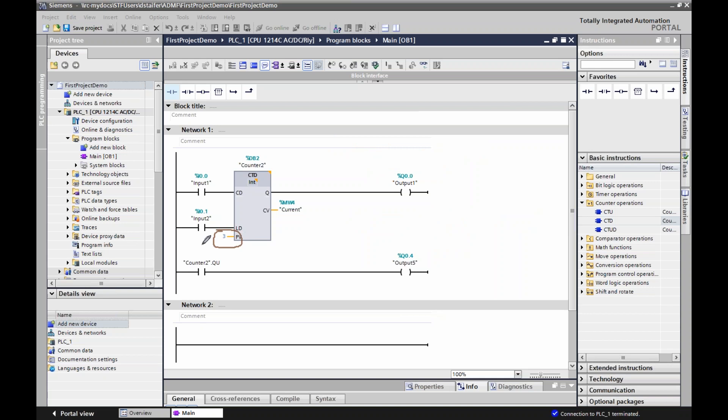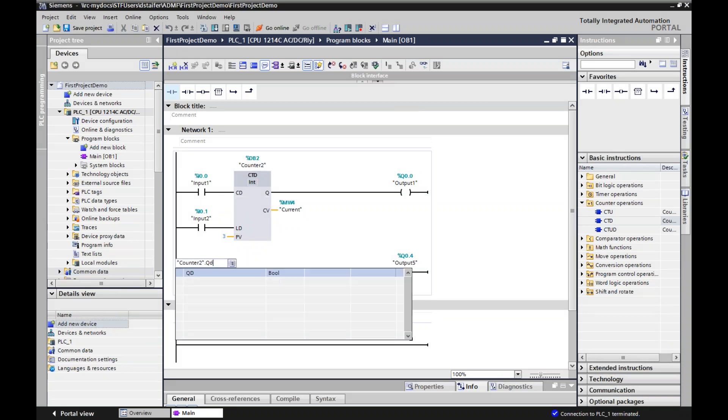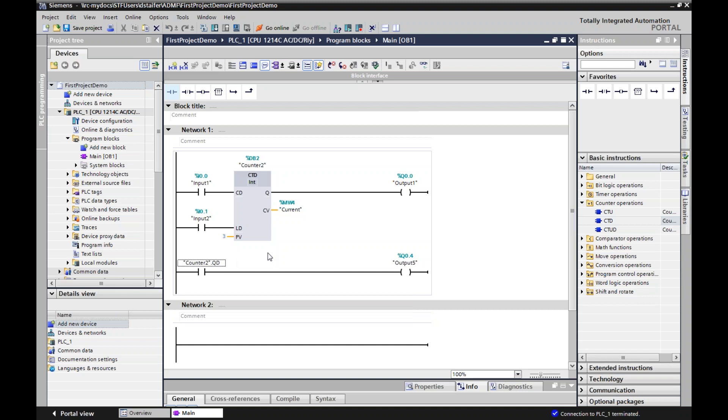But in a CTD, it takes the current value and changes it to the preset value. So this is the reset, and this is a load. So in the count up, the reset takes the current value, makes it zero. In a countdown, it takes the current value and makes it your preset value. Here is my preset value, because the Q will only go true when this equals zero.